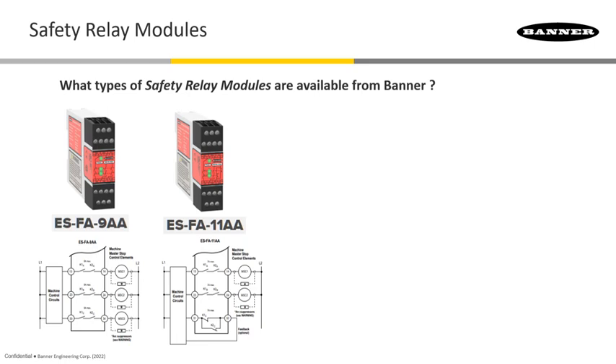The ESFA-9AA has three normally open contact paths available, rated at 6 amps. The ESFA-11AA has two normally open contacts rated at 7 amps, plus a normally closed auxiliary contact also rated at 7 amps. These can be used for enunciation of the module state, taking the connection back to a PLC or a warning light, for example.